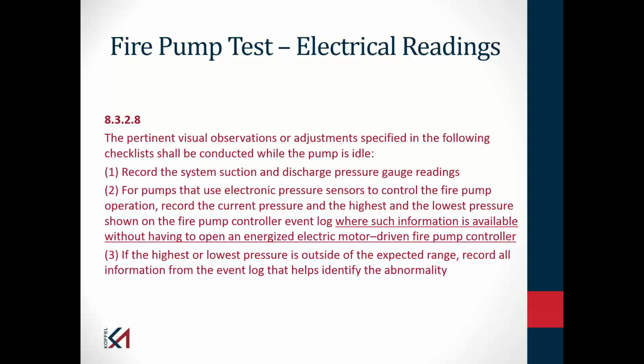And then the last one I want to talk about is the fire pump test. While this is new to the 2020 edition, we actually also issued this change as what's called a tentative interim amendment. So we did go back and revise the 2011, 2014, and 2017 editions of NFPA 25 with a TIA. And what that says is if you cannot read volt and amp readings without opening up the controller door and taking those readings inside the controller, you do not have to take those readings. The concern is arc flash and the hazard associated with it, and the committee determined that that's a more significant hazard than having a fire pump where we know flow and pressure, but we don't know what the amps and volts are that it's operating at.